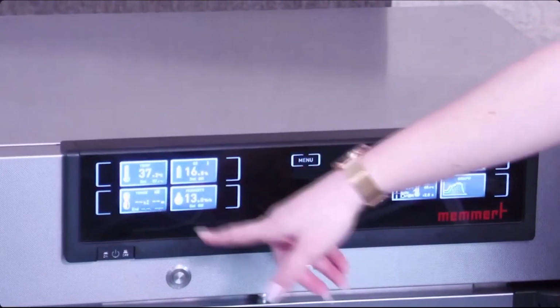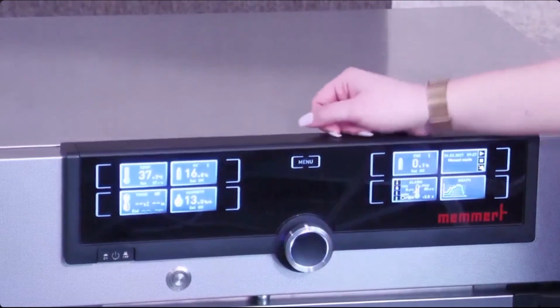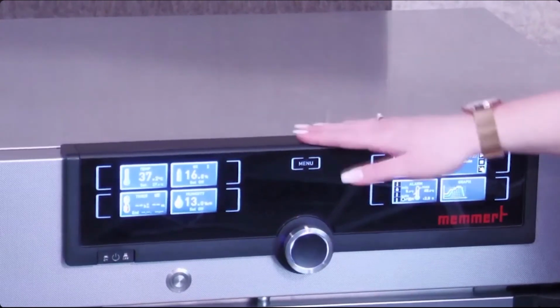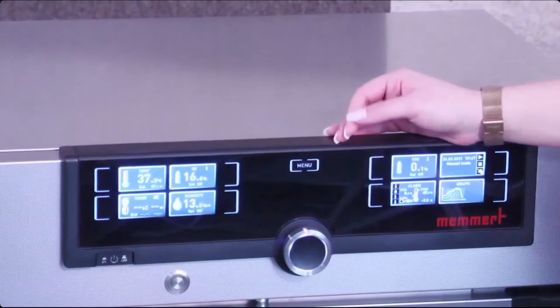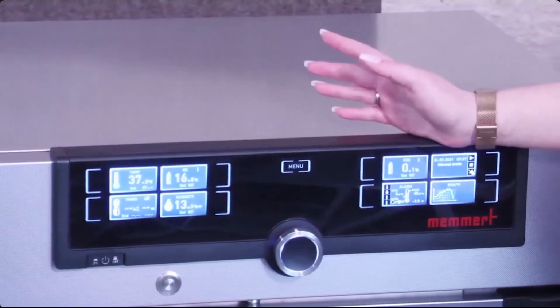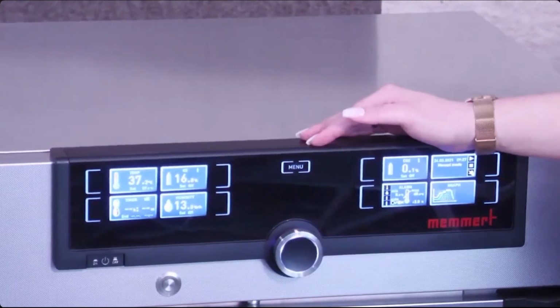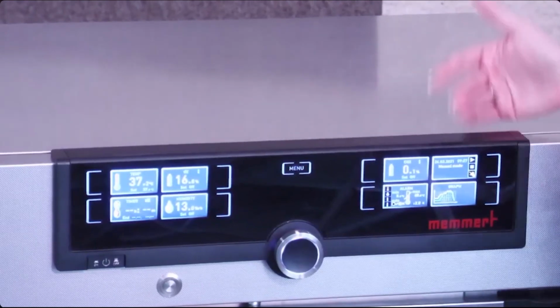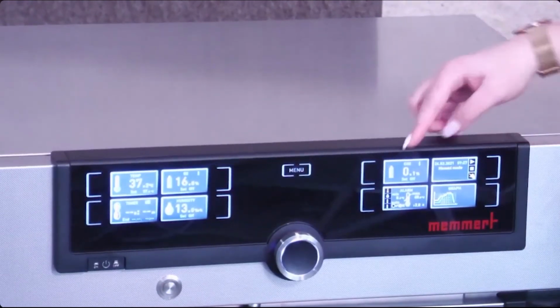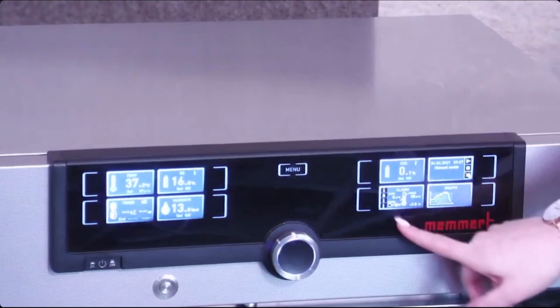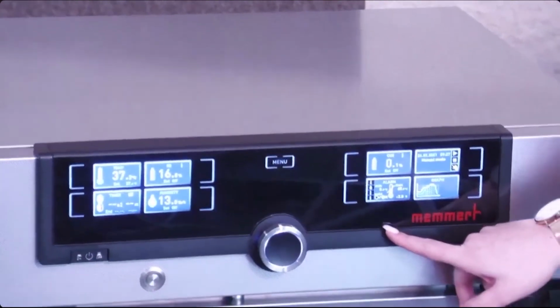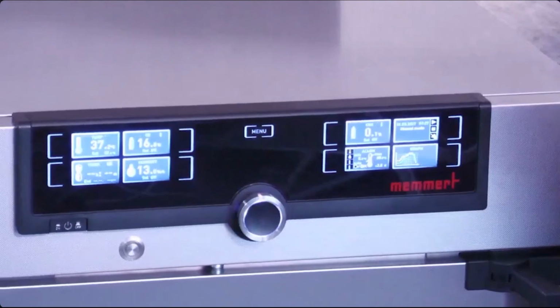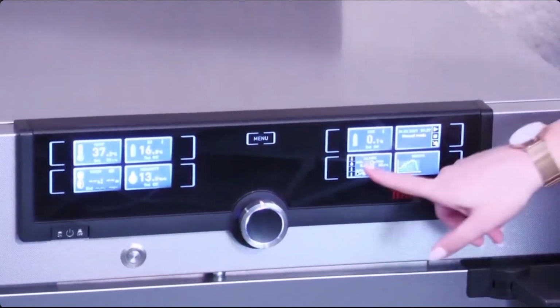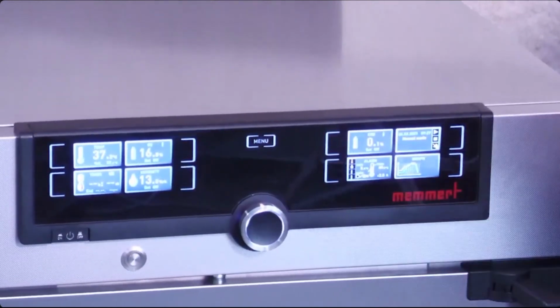You can set a timer to count down the process time. We also include a set point wait function, which means the timer will not start running until your desired set temperature has been reached. Having a look at the other hand, we can see our CO2 control over here. We're having different alarms over there. The alarm values can be set individually for every customer and for each parameter, depending on their preferences.